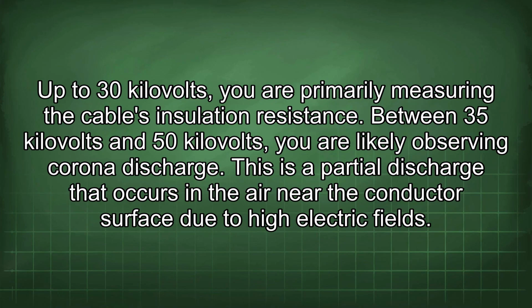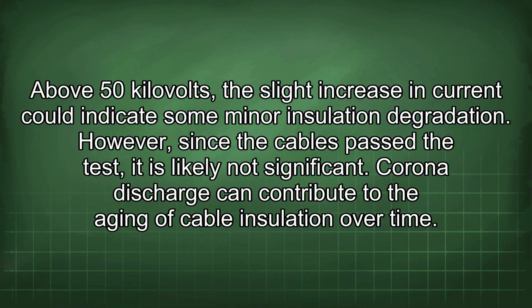Up to 30 kilovolts, you are primarily measuring the cable's insulation resistance. Between 35 kilovolts and 50 kilovolts, you are likely observing corona discharge. This is a partial discharge that occurs in the air near the conductor surface due to high electric fields. Above 50 kilovolts, the slight increase in current could indicate some minor insulation degradation. However, since the cables passed the test, it is likely not significant.